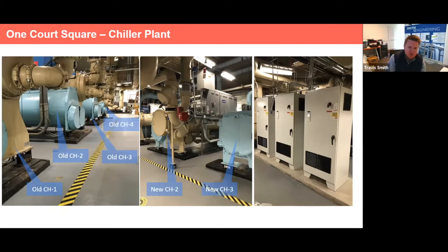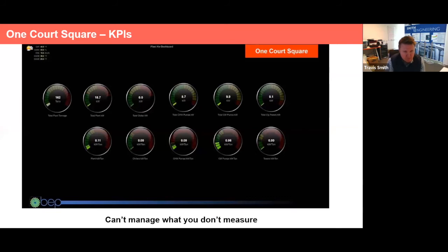So improved maintenance on the equipment that we maybe don't talk about too much. The old adage, you can't manage what you don't measure. I think we've all preached it for a long time, and in a lot of buildings it hasn't come to fruition. You can see here we have total plant tonnage. This is a plant KPI screen, key performance indicator screen. You have total plant kW per ton, chiller kW per ton, and chilled water pump, condenser water pump, towers.